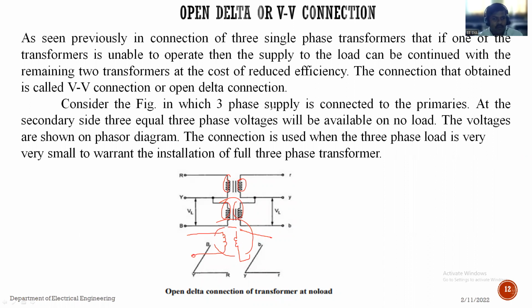In that one winding it is open circuited, or it may be burnt. So there is an open circuited terminal, and similarly the primary and secondary of one transformer may be removed. Meaning, one of the three single phase transformers is removed. So it will make an open delta connection.